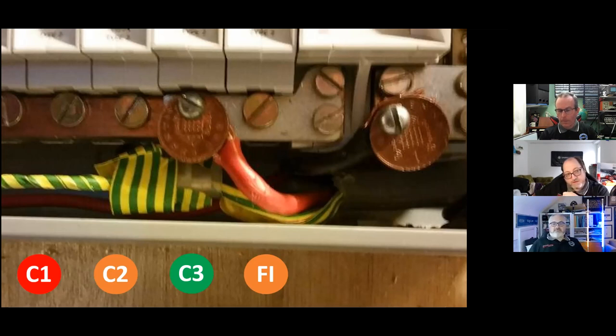So what do you do? You walk in, you see that. What code do you put for that? What do you think, JW? That one, I put C2. Why? Because it's not an approved connection method. And someone's put in the chat that copper coins conduct really well. Well, copper coins aren't actually made of solid copper, so conductivity is a question in that one.